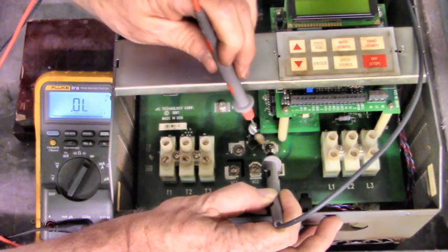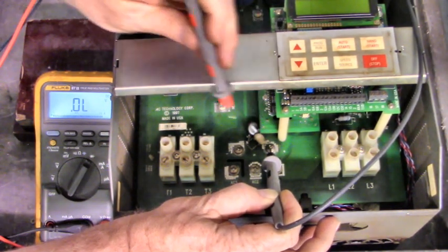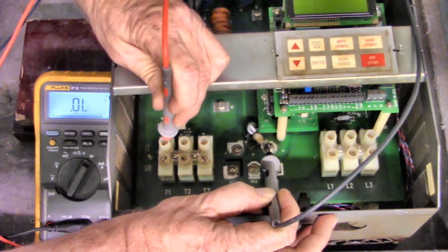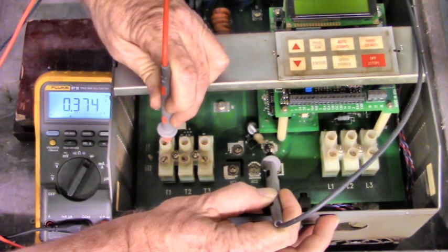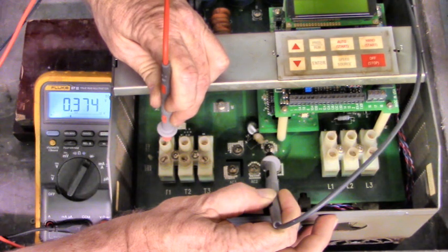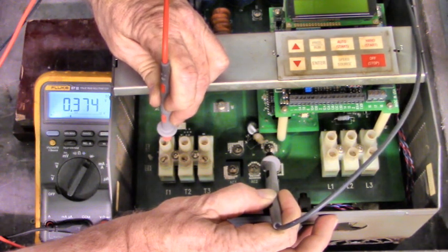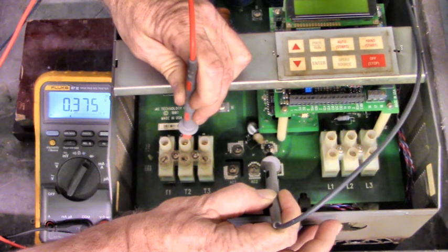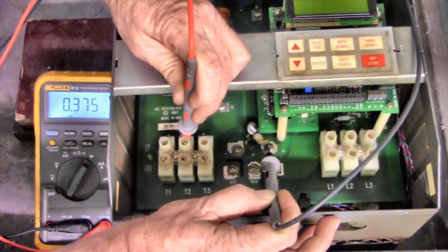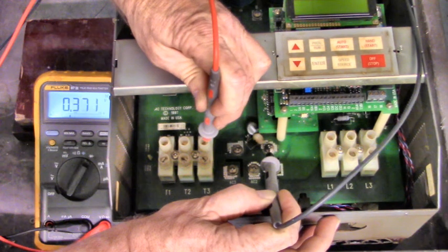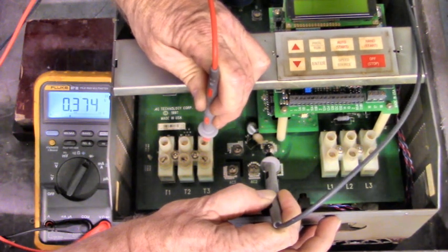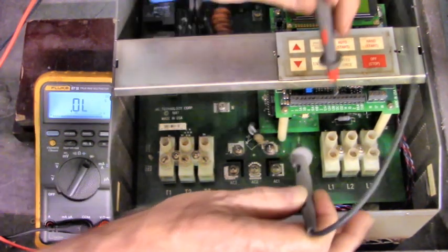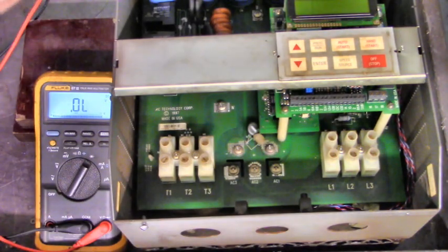Leave your black lead on three-phase bridge plus, and we'll go to the motor. Get on there. With the red lead on T1, you've got .374. T2, .375 volt diode drop. That's good. Now, that's high side on everybody.